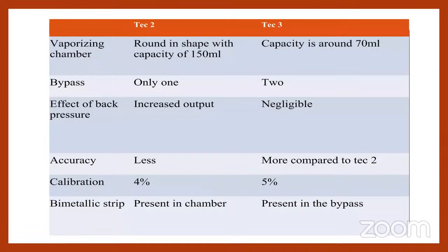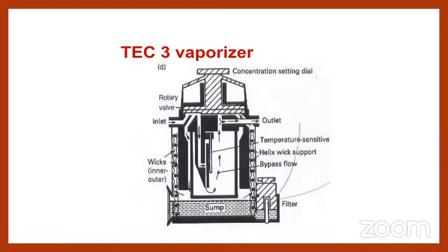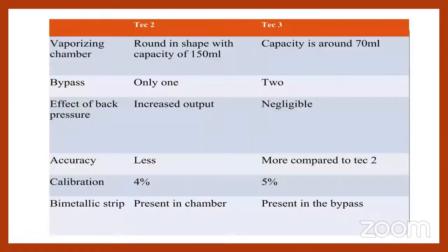The bimetallic strip is present in the chamber in Tec 2 vaporizers, whereas in the Tec 3 vaporizer, it is present in the bypass. So this is the metallic strip, as you can see here. This is the metallic strip which is present in the bypass channel, whereas this is the vaporizing chamber. So some amount of gas will enter the vaporizing chamber here, and it mixes with the vapor inside the vaporizing chamber, whereas the metal strip is present in the bypass pathway. So the amount of fresh gas that enters the system will be regulated by the temperature and volume, depending on the vaporizing capacity and other factors which are involved with it.